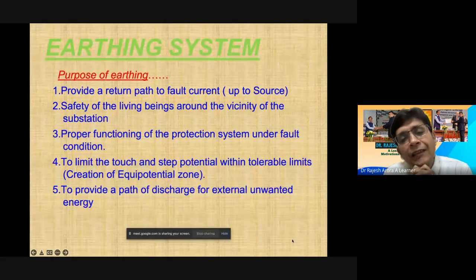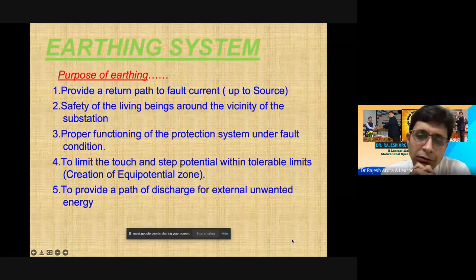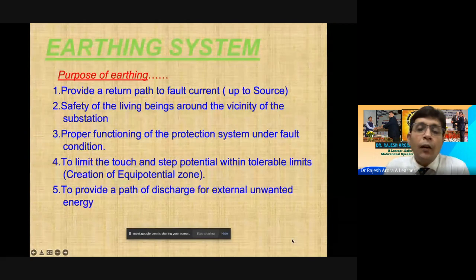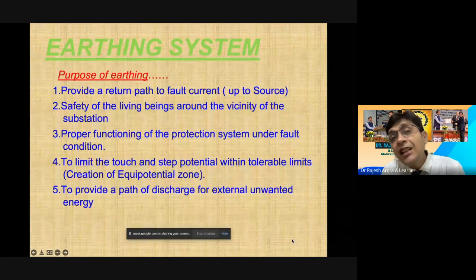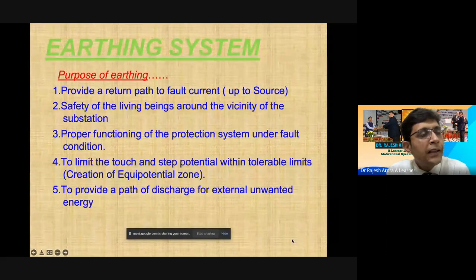We have to take care of the living beings around the vicinity of the substation or the premises where we are providing that system. The functioning of the protection system under fault conditions, especially SLG, single line to ground fault, is also important. That is the most common fault in our electrical system. 98% of faults comprise SLG. You need a proper earthing system so that the protection system installed can isolate the faulty portion quickly.